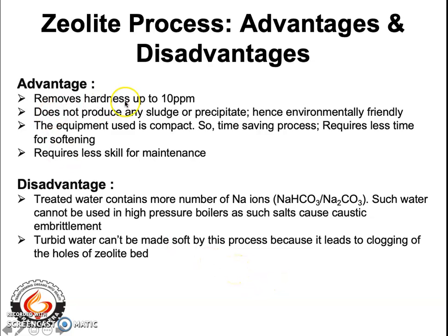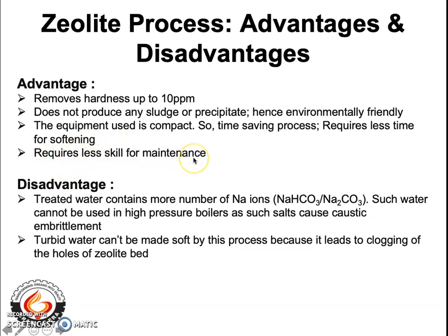The advantages of the zeolite process are: it removes hardness down to a level of 10 ppm; it does not produce hard precipitates or sludge, making it environmentally friendly; the equipment used is compact, reducing treatment time; and it requires less skill for maintenance.